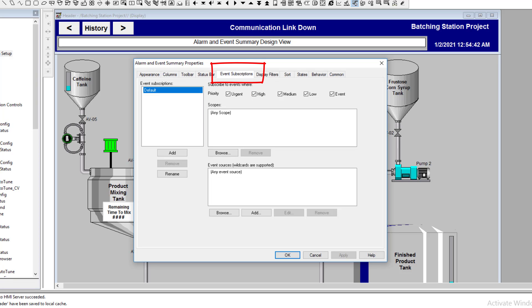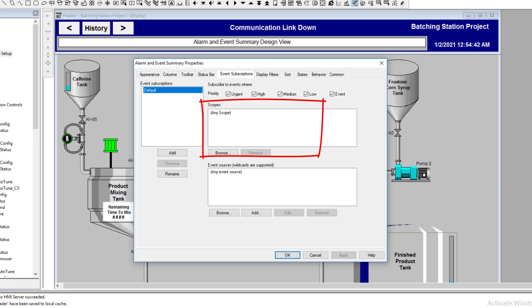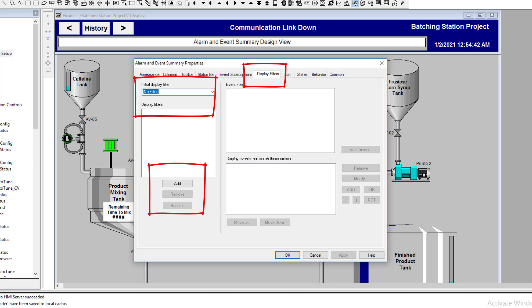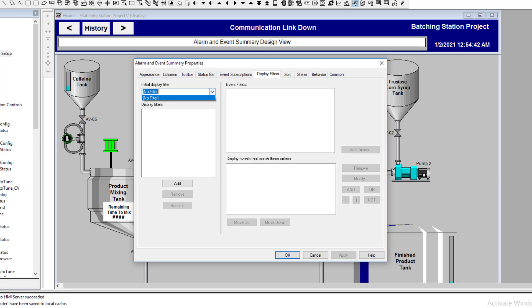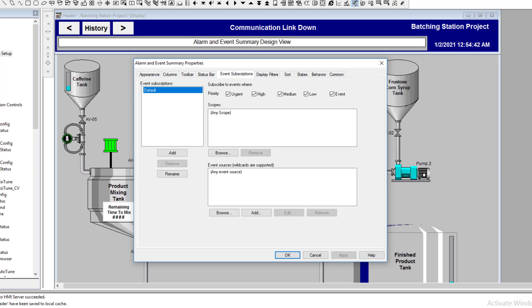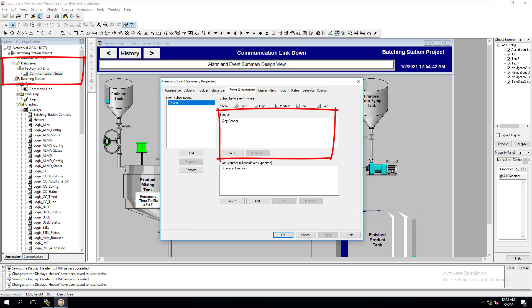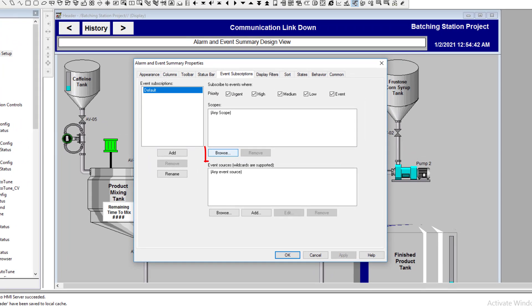The more important thing is changing our Scope. In here you can add filters. If you have a large application, this is where you'd add filters — for example, if Display equals a certain value. In our case we only have one application, one shortcut, so we don't need filters. To connect the Alarm and Events Summary to actually read our alarms — which we'll program in our ControlLogix processor — we need to tie in the data server via FactoryTalk Linx.